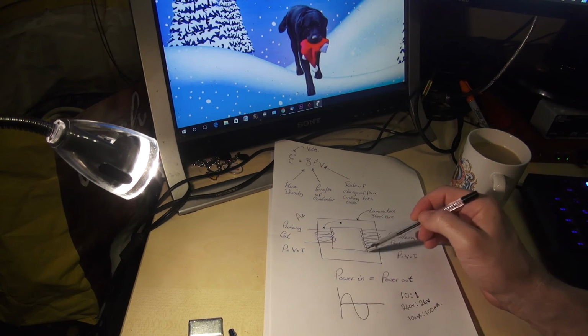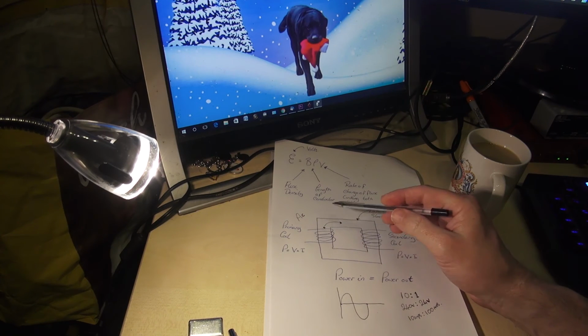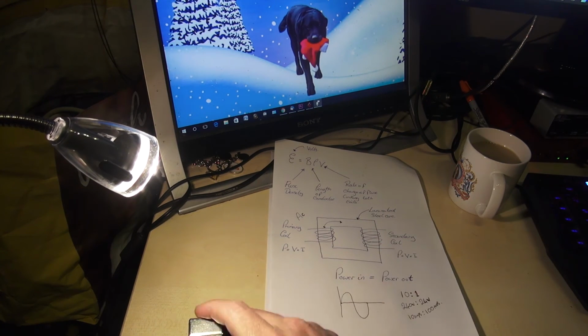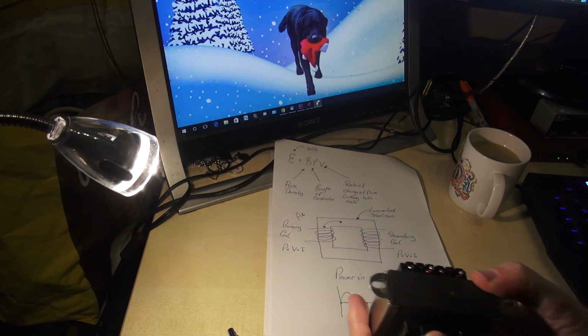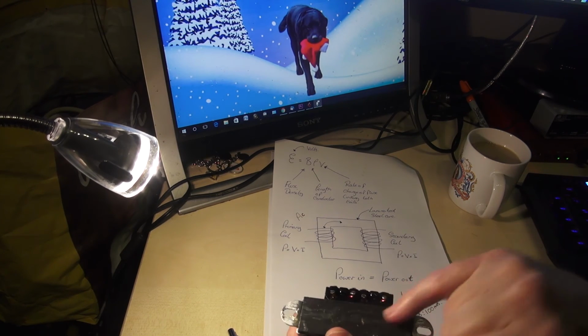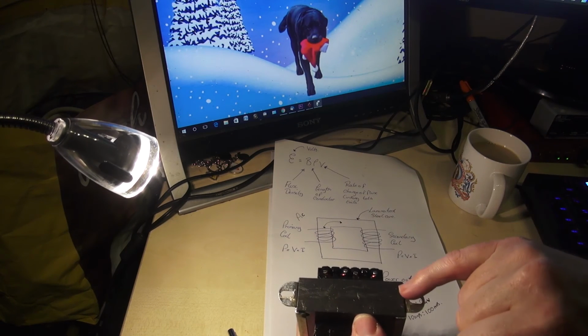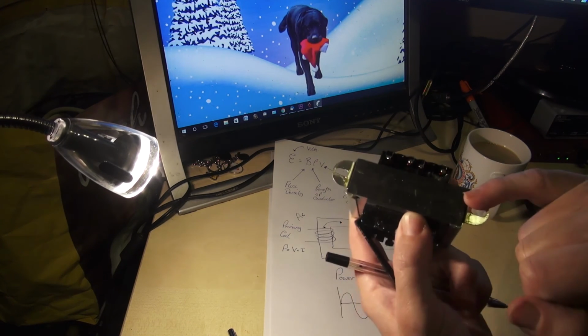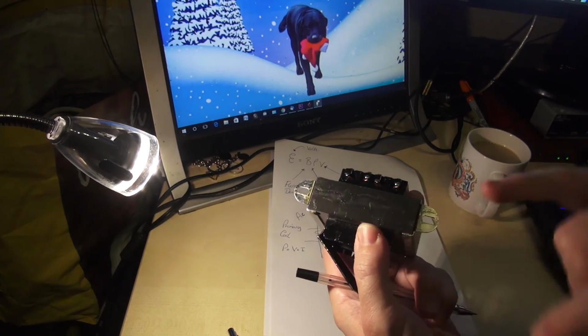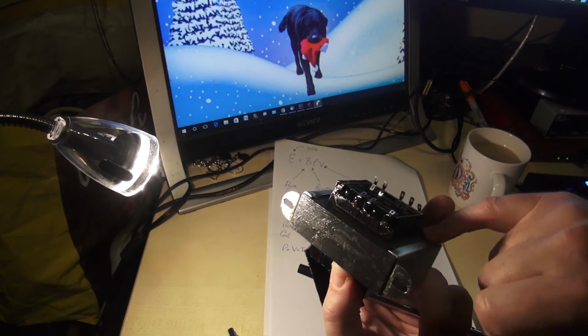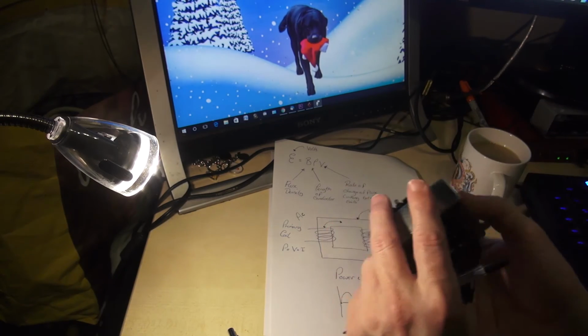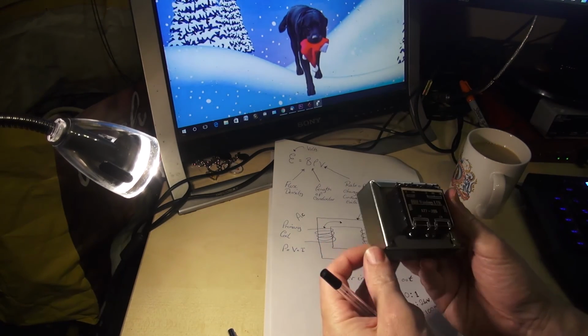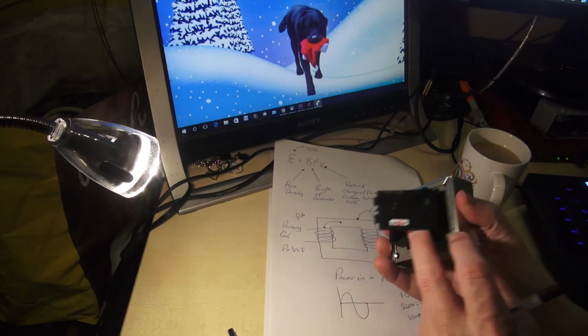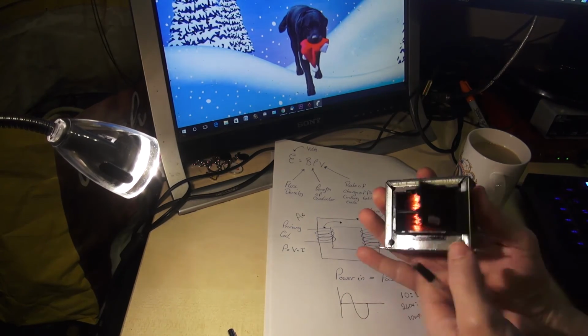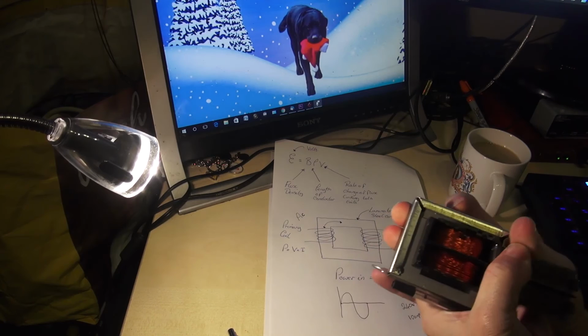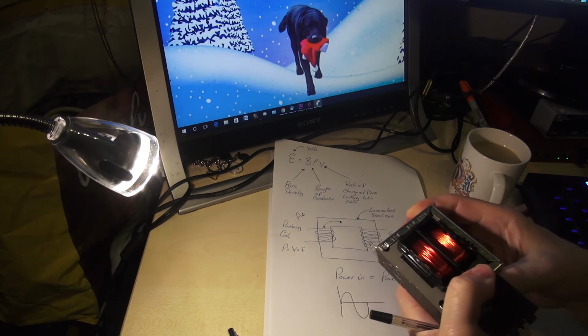The reason for the laminated steel core is that currents flowing through the transformer actually cause power loss. The laminations stop a phenomenon called eddy currents flowing across the surface of the core, which causes power loss. Transformers are probably one of the most efficient machines we have, usually about 98% efficient.